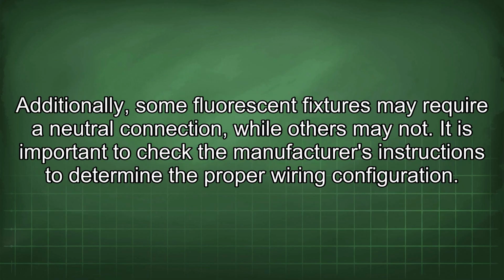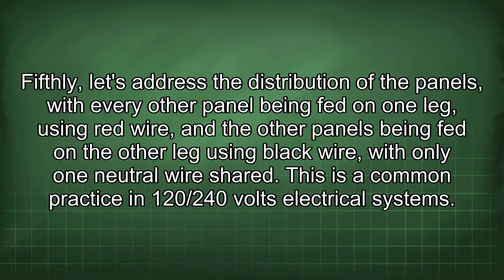Additionally, some fluorescent fixtures may require a neutral connection, while others may not. It is important to check the manufacturer's instructions to determine the proper wiring configuration. Fifthly, let's address the distribution of the panels, with every other panel being fed on one leg using red wire and the other panels being fed on the other leg using black wire, with only one neutral wire shared.